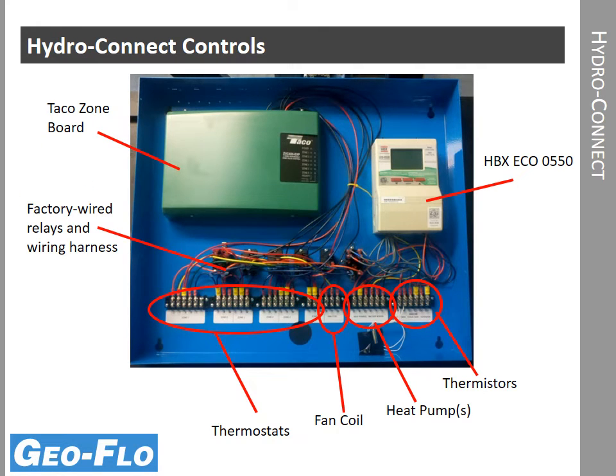This is what the control panel looks like. You can see here the green Taco Zone Board, the HBX controller on the right, and then in the middle of that control box are the factory installed relays, as well as the wiring harnesses. So the end result is that all the connections are down at the bottom. In this case, we have the zone panel that has 1 fan coil zone and 5 radiant zones. There are other versions as well, but they all have similar connections so that all of the connections are made at the bottom, and the factory wiring greatly simplifies the system. We've decided to use zone 1 as the master thermostat if it's a heating and cooling panel, and that will determine whether the tank is heated or cooled, unless the warm weather shutdown or cold weather shutdown tells it that it's not necessary.